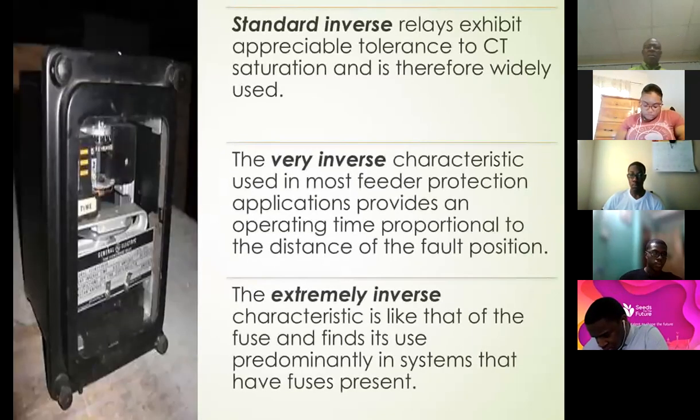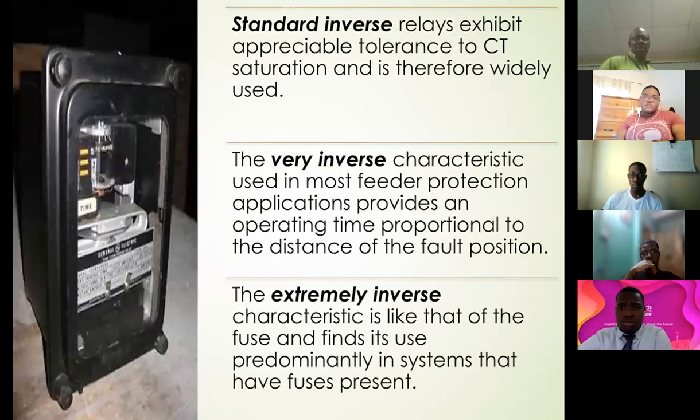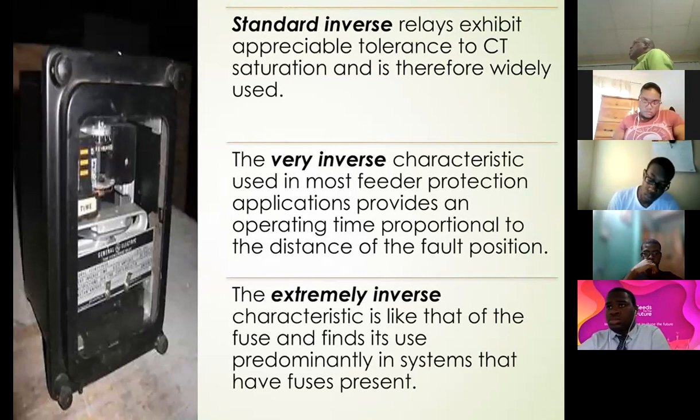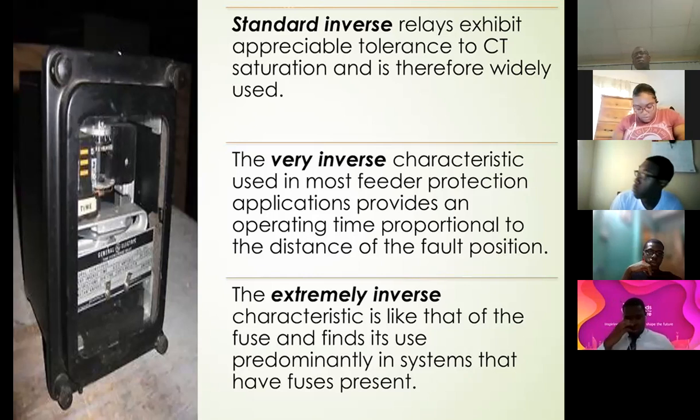So for your standard inverse, your standard inverse is going to show what we refer to as appreciable tolerance to CT saturation. So where you're running the risk of having your CTs saturated, the standard inverse relay will treat with it.